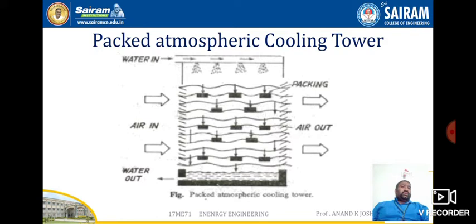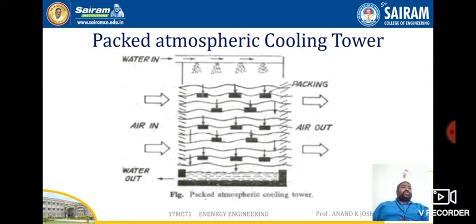The packed atmospheric type cooling tower differs from the spray fill tower in that a fill material is used to break the water into small droplets. Air flow is crosswise to the water flow. These towers are also rarely used, even for small thermal power plants, due to the high original cost, high pumping height required, and the need for extreme length, height, and narrow width to withstand high winds.